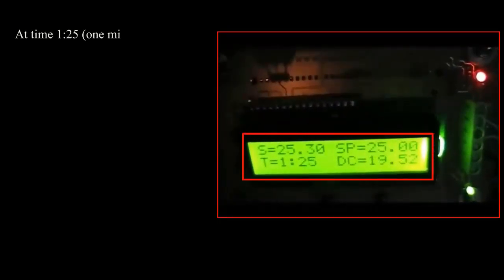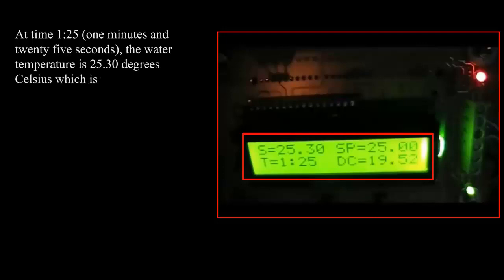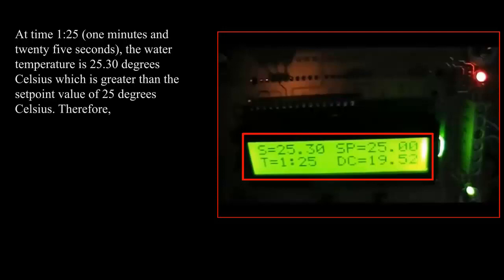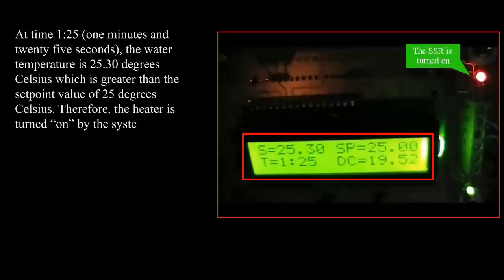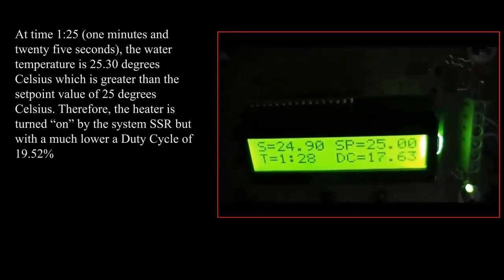At time 1 minute and 25 seconds, the water temperature is 25.30 degrees Celsius, which is greater than the setpoint value of 25 degrees Celsius. Therefore, the heater is turned on by the system SSR but with a much lower duty cycle of 19.52 percent.